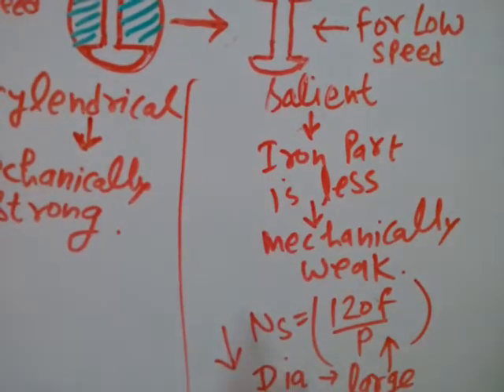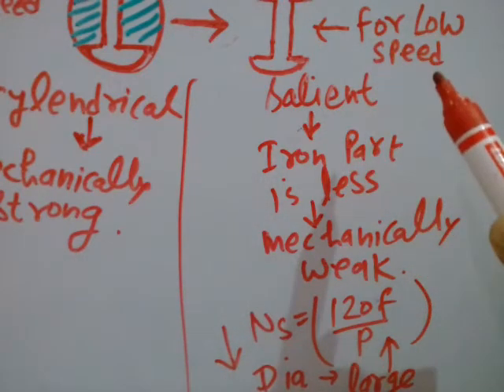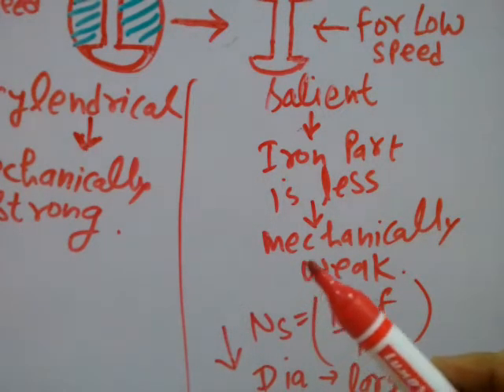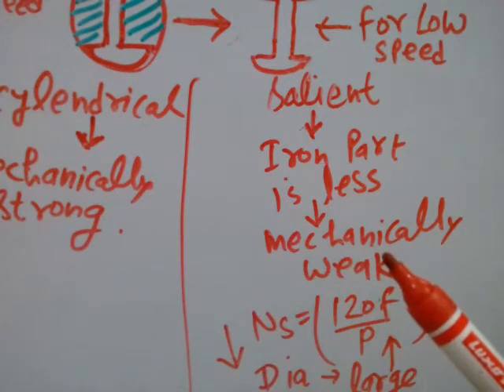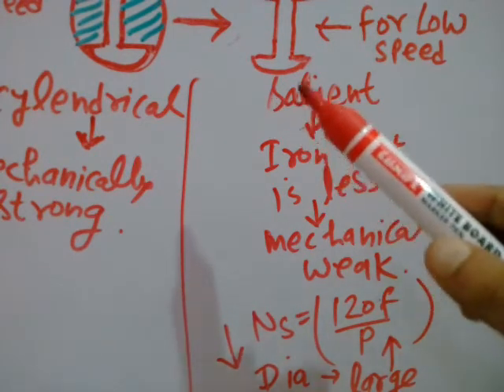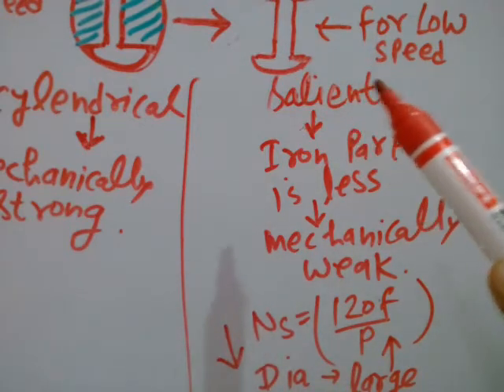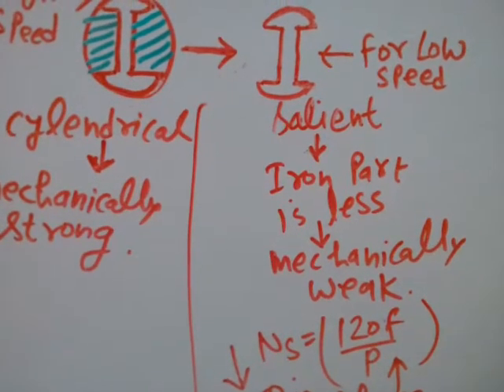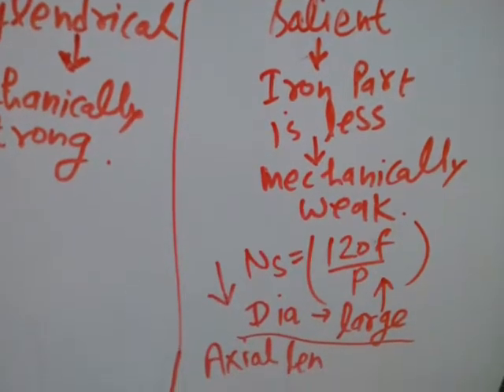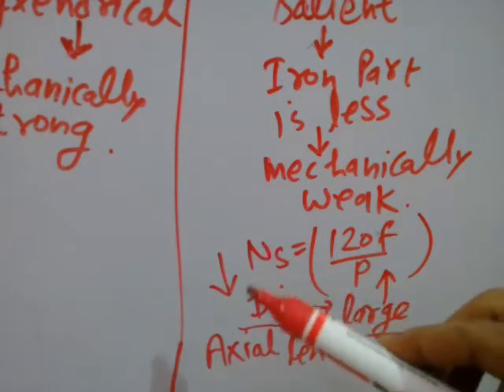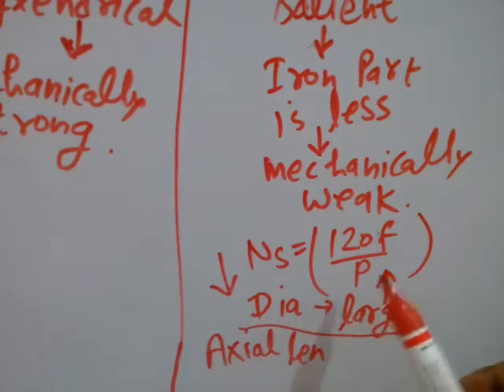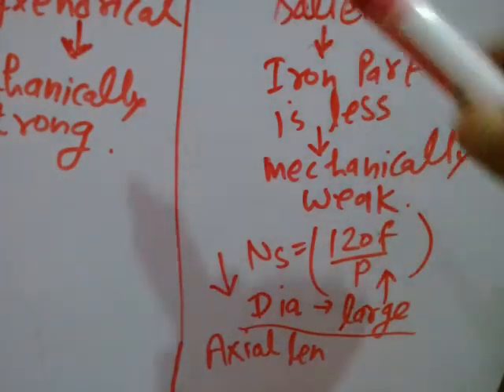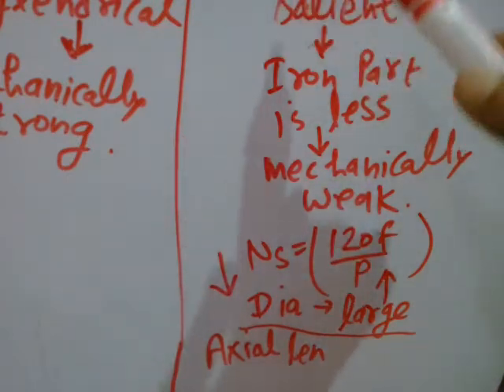Salient pole rotor structure is used for low speed because of its low mechanical strength — it is mechanically weak, so you cannot operate this salient pole structure at high speed. You can only operate it at low speed. If the speed is low, then the number of poles will be high, meaning if you want to accommodate a large number of poles on the same periphery, the diameter will be large.